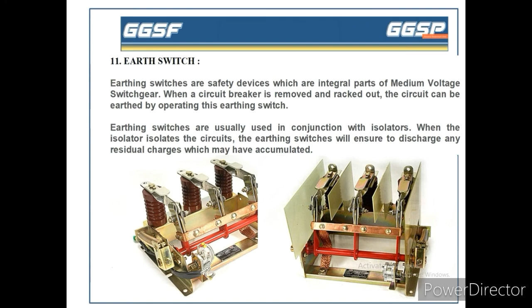Earth switch: earthing switches are safety devices which are integral parts of medium voltage switchgear. When a circuit breaker is removed and racked out, the circuit can be earthed by operating this earthing switch. Earthing switches are usually used in conjunction with isolators. When the isolator isolates the circuit, the earthing switches will ensure to discharge any residual charges which may accumulate.